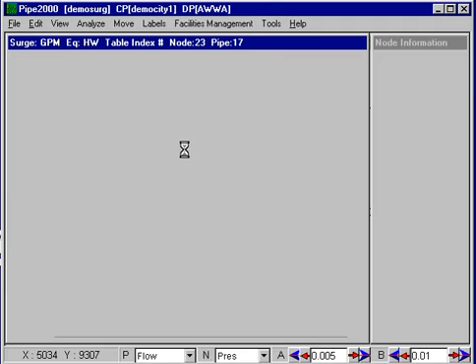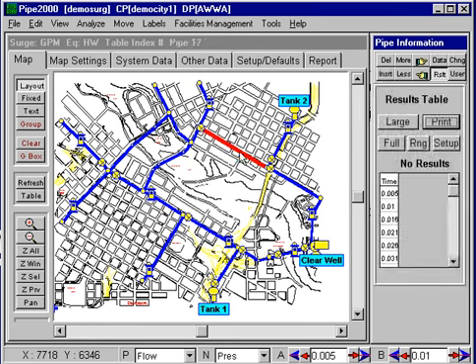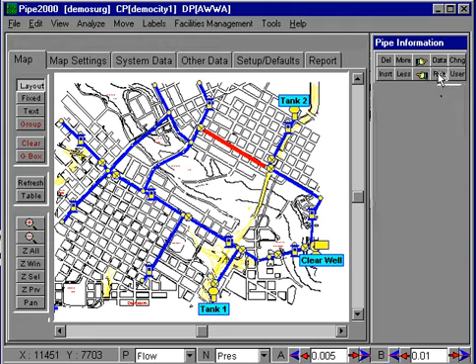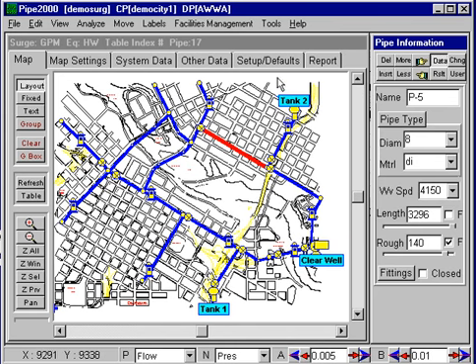As far as the basic data for the pipes and nodes, the additional data required for pipes is the wave speed — that is essential data. The wave speed is a parameter that's required for surge analysis. The best way to enter this data is to include it in the pipe type table, and then it will automatically be entered when you select the pipe.